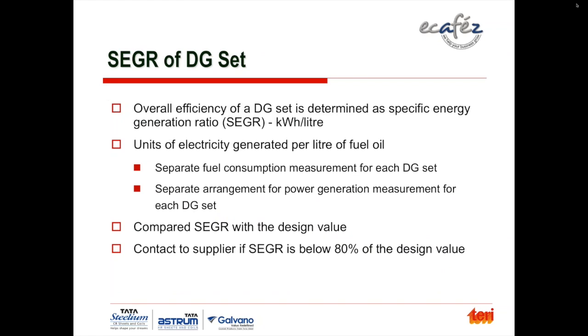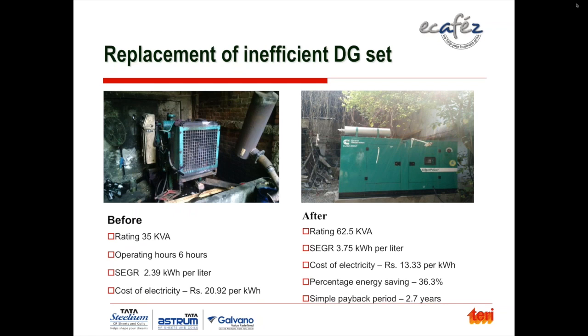Now, moving to another equipment, on the DG side, of course, I mentioned that the loading in the DG set is important. One of the critical parameters in the DG set is the specific energy generation, that is, how many units of electricity you generate per liter of diesel. This specific energy consumption has to be compared with the design value of the DG sets. What you are getting now can be recorded and compared to the design. If it's below 80% of design, it is recommended to consult the supplier of the DG sets. Now this is an example of an inefficient DG set replaced by an efficient DG set, because here it was beyond repair.